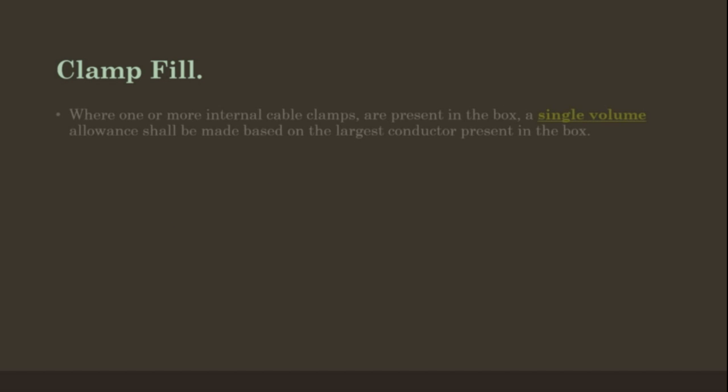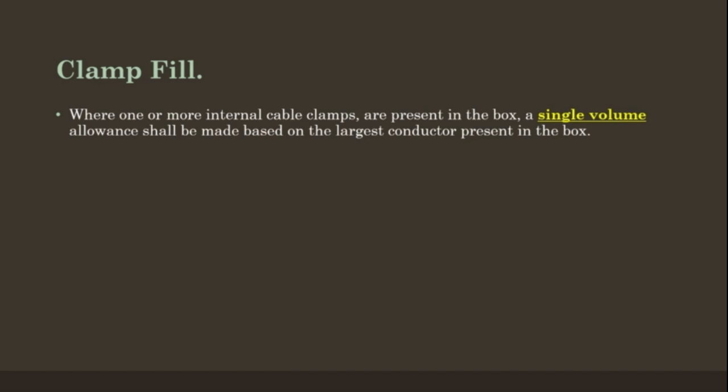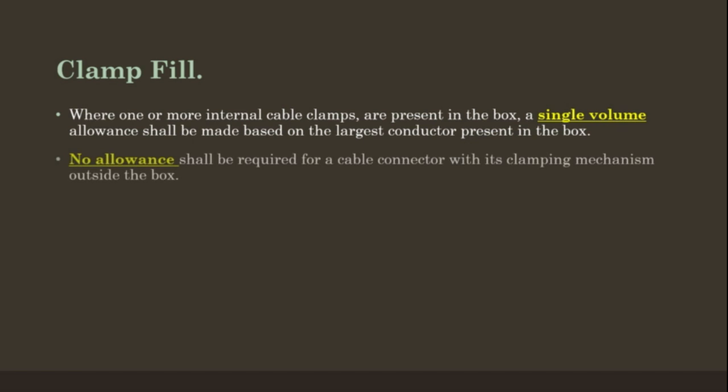Clamp fill: Where one or more internal cable clamps are present in a box, a single volume allowance shall be made based on the largest conductor present in the box. No allowance shall be required for a cable connector with its clamping mechanism outside of the box.